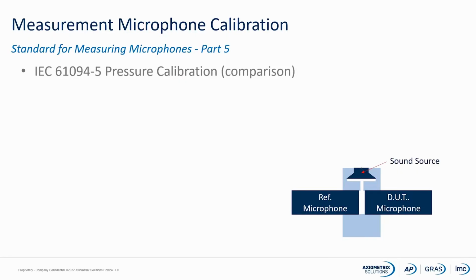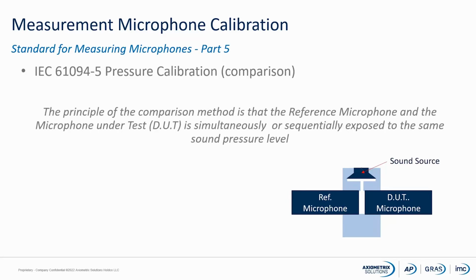If we look at measuring microphones, then we are going to look at part 5. And the first we will look at is the pressure calibration comparison. And the principle is that you have a reference microphone, you have the microphone under test, and then you have a sound source. So these two microphones will see exactly the same. If you know the exact sensitivity of your reference microphone, then you can easily find the sensitivity of your microphone under test. And that's the principle.